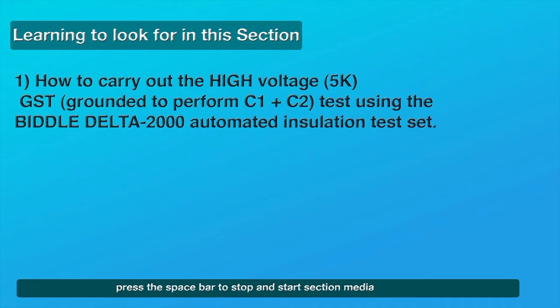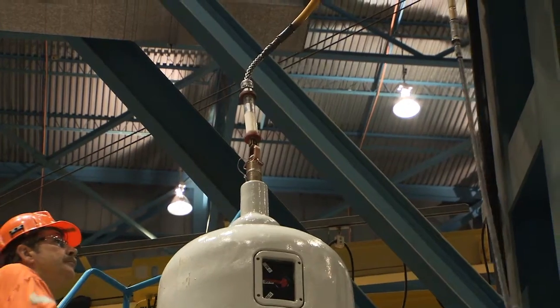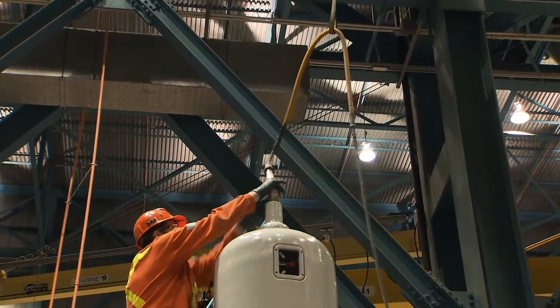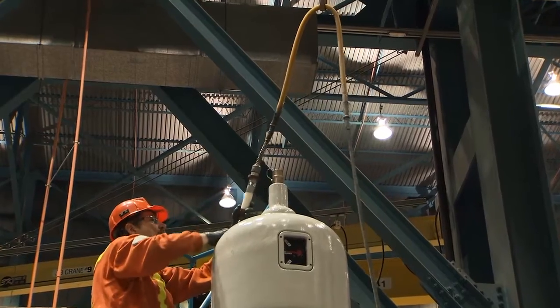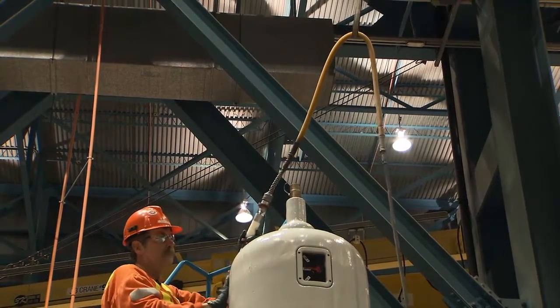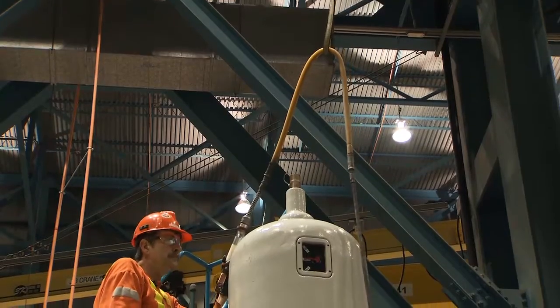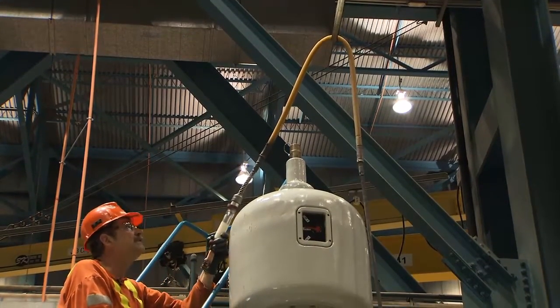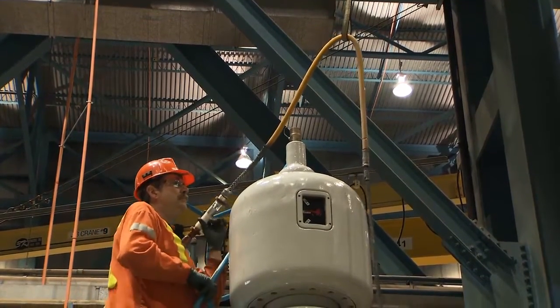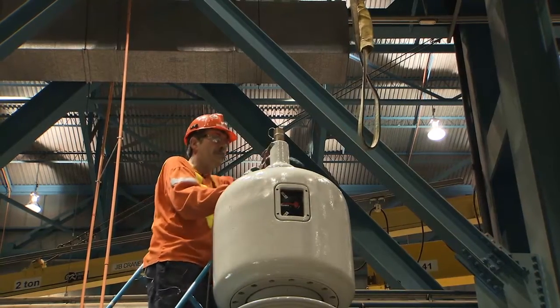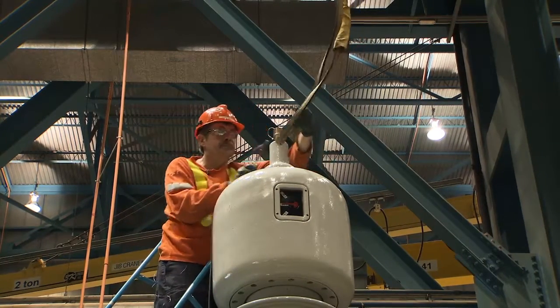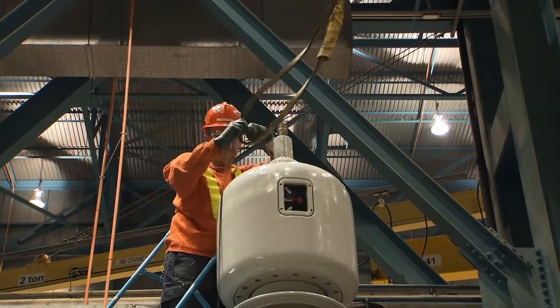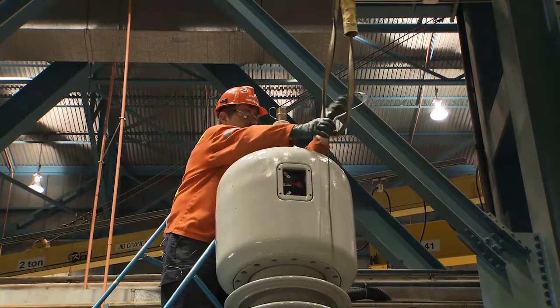The final high voltage GST electrical test, C1 plus C2, for capacitance and dissipation factor. To make the connections for the C1 plus C2 GST test, disconnect the high voltage lead at the top of the bushing. Support the low voltage lead cable through the end of the sling suspended by the hoist hook above the bushing.